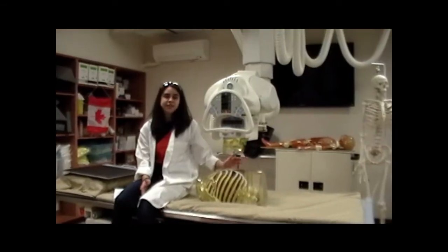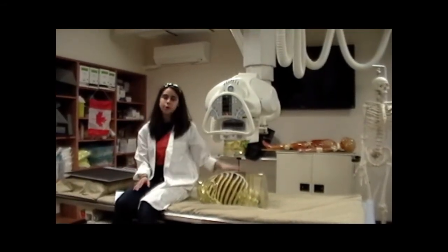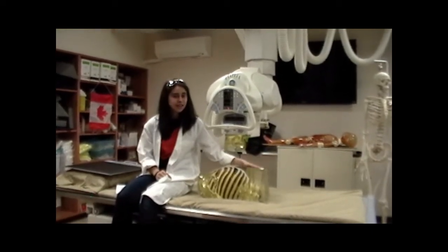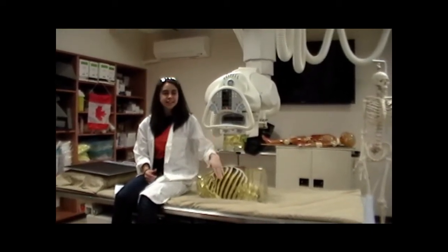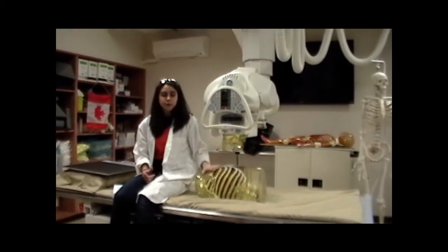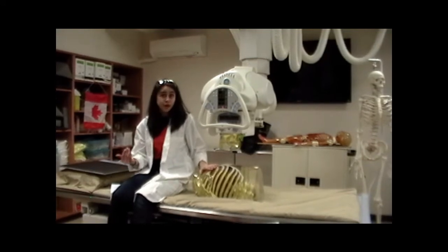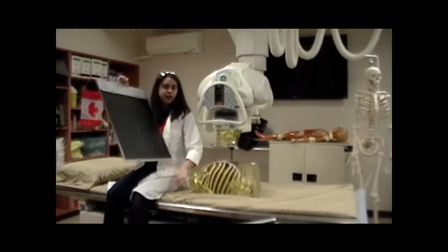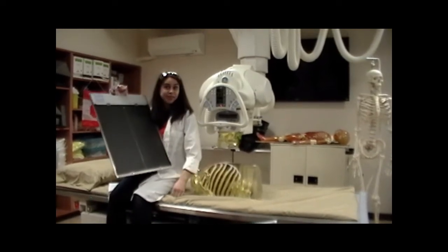Those beam restricting devices make sure those off-focus X-rays don't reach the body. But the number one place scatter is created is the body itself. It's those X-rays that get deflected when traveling through the body, creating fog on the image receptor. The more fog, the worse the image quality due to the lower contrast. You can decrease this by putting a grid in front of the IR and behind the patient. It'll clean up the image.